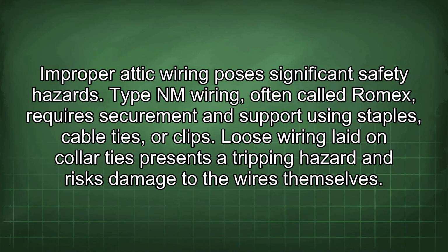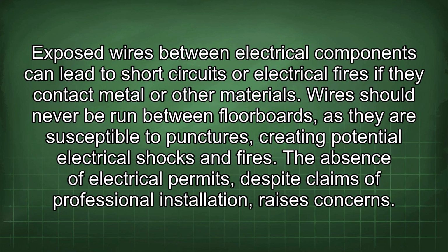Improper attic wiring poses significant safety hazards. Type NM wiring, often called Romex, requires securement and support using staples, cable ties, or clips. Loose wiring laid on collar ties presents a tripping hazard and risks damage to the wires themselves. Exposed wires between electrical components can lead to short circuits or electrical fires if they contact metal or other materials.